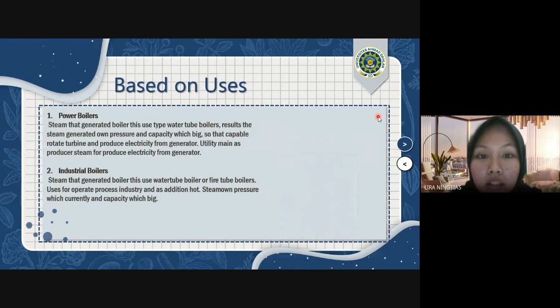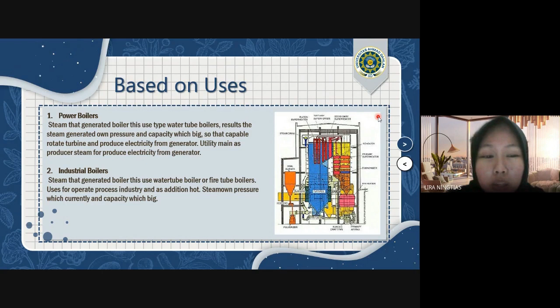Based on uses. 1. Power boiler, the steam generated by the boiler. This uses the water tube boiler type. The steam is generated at big pressure and capacity, so it is capable of rotating a turbine and producing electricity from a generator. It is the main utility producing steam for electricity from a generator. And 2. Industrial boilers, steam generated by the boiler. This uses a water tube boiler or fire tube boiler. It is used to operate industrial processes and as additional heat. Steam at medium pressure and big capacity.